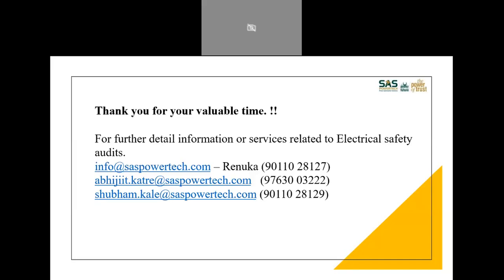Is it necessary to replace transformer oil every year? And if yes, then why? Definitely not every year. See, I missed that in the total presentation. Good that this question has come. Normally, transformer oil needs to be filtered every year, not replaced. Filtered every year because the transformer gets exposed to all environmental conditions, and it's a fossil oil, so sludge formation and all that is possible.